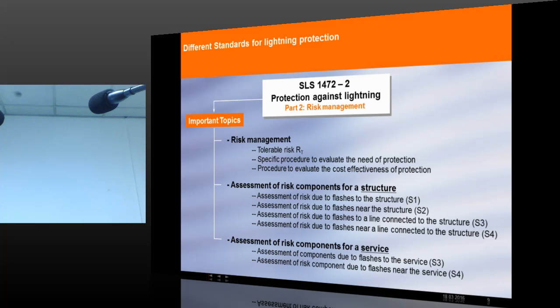Now we go to part number 2, risk management. Risk management talks about the primary thing, which is tolerable risk. Tolerable risk means under a lightning, out of maybe how many lightning strikes in a particular installation, a failure is acceptable. Let's say a failure of an electrical system. Out of how many lightning strikes? See, before that, 100% lightning protection is impossible for your information. We can only achieve a maximum of maybe 99.5 or 99.8% protection.